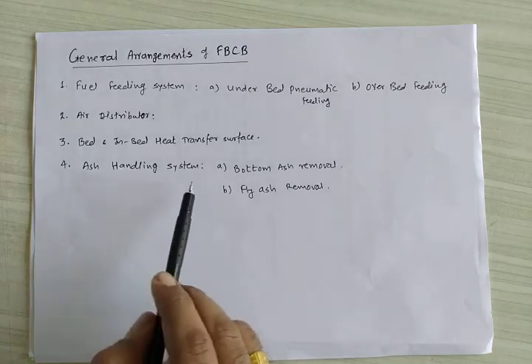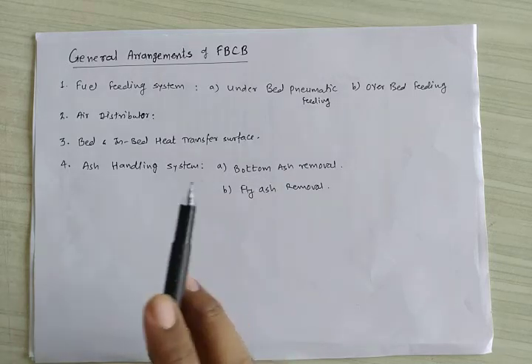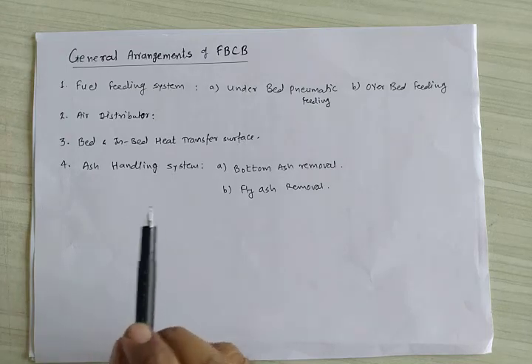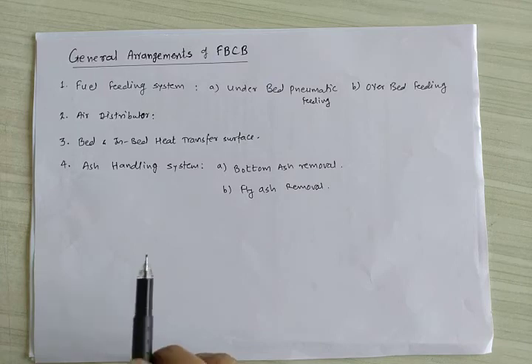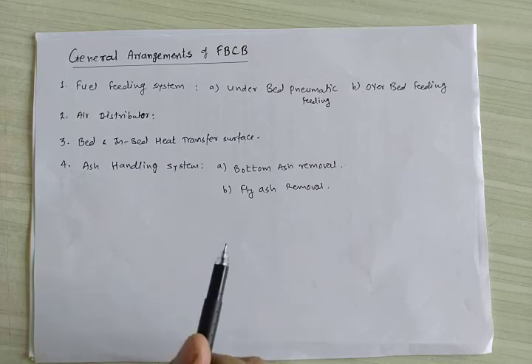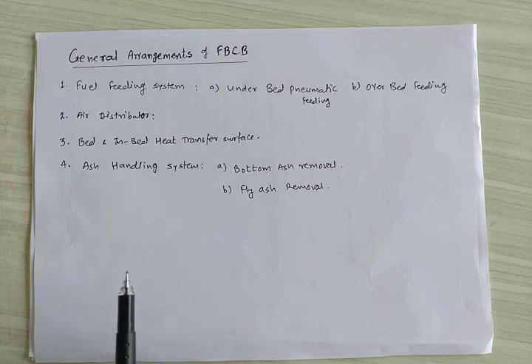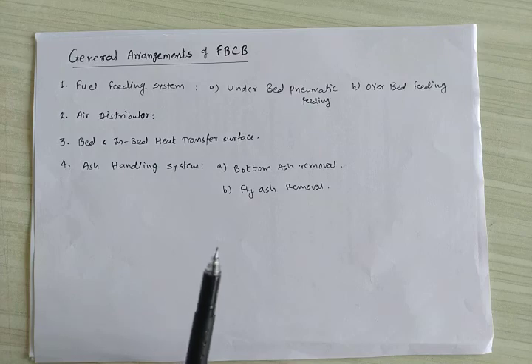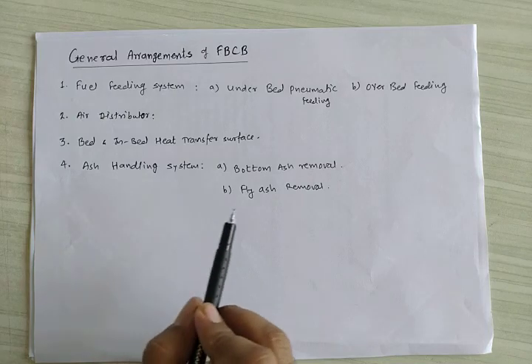In the ash handling system, bottom ash removal handles 40% of total ash. The fly ash amount to be handled in an FBC boiler is relatively high compared to conventional boilers, due to separation of particles by size and shape at high velocity. Fly ash should be removed in three stages: first in the convection section, second from the bottom of the air preheater, and finally a major portion is removed in the dust collector.